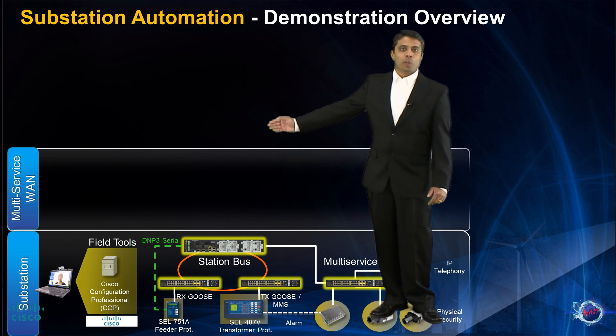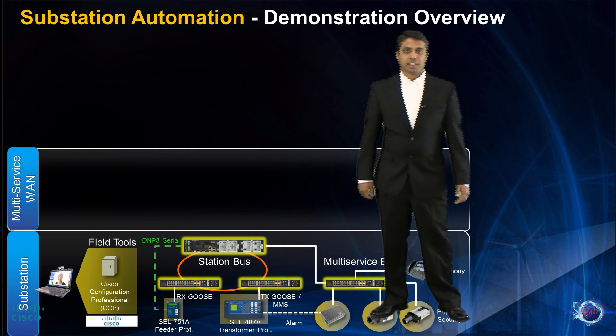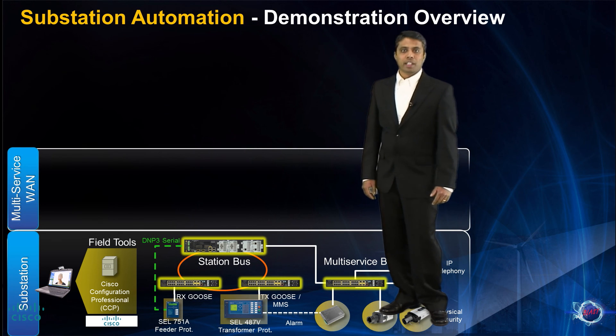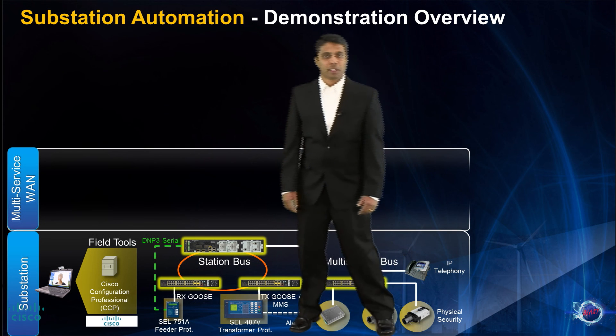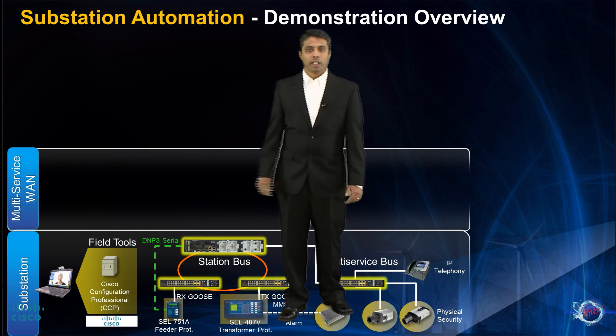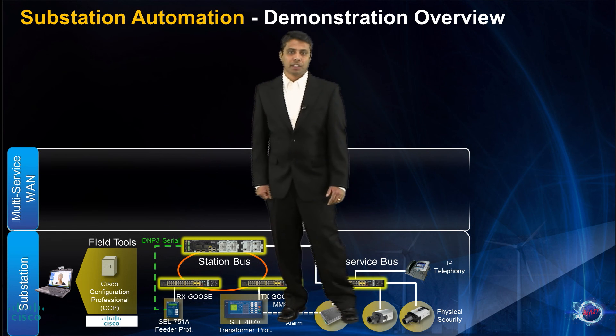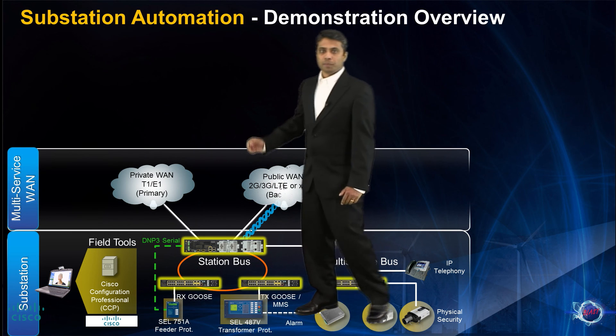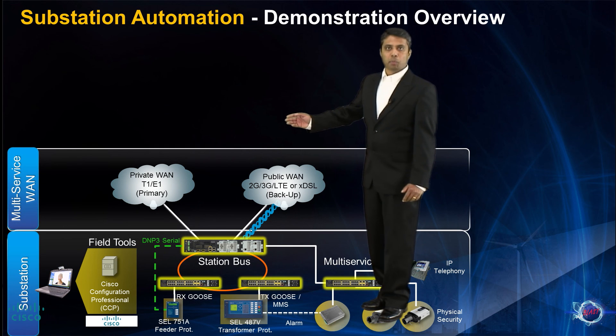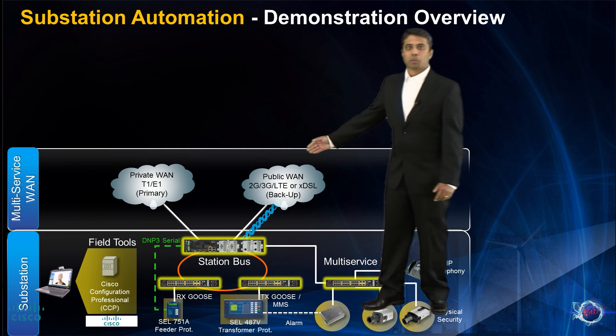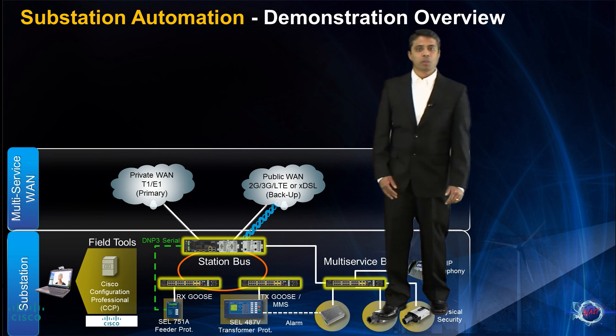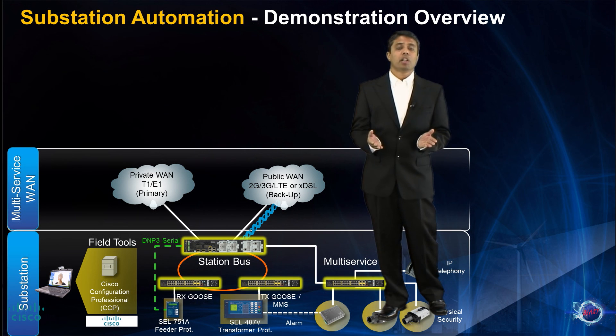The wide area network, or WAN, can be a wired or wireless connection. The CGR2010 can offer various network connectivity options including advanced VPN technologies for traffic segmentation, and security technologies like firewall and encryption to provide the electronic security perimeter at the substation. T1/E1 or Ethernet are typical wired connections. DSL is also an option, which is more popular in Europe for substation connectivity. It also supports cellular connectivity like 3G and the latest 4G LTE technologies, which are typically used for backup connections but may also be used as a primary WAN connection in smaller or less critical substations.